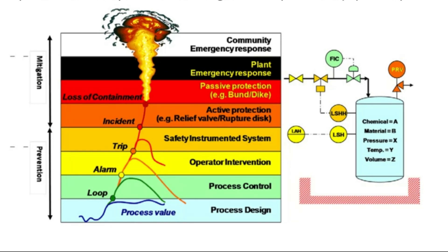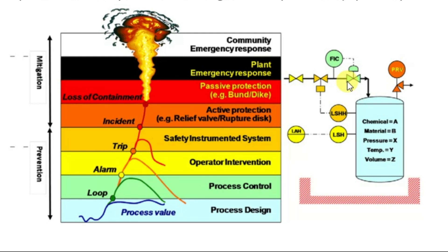A plant has to operate in the safe zone — the green zone. And then further, when limits are exceeded, we can understand this using a small P&ID. There is a chemical tank which has a hydrogen chloride facility, for example. The required chemical is being sent into the tank using an isolation valve, emergency block valve, and flow control valve. Inside the tank, pressure, temperature, and volume (level) are being measured. Based on the level, if the level is going down, the control valve operates using a flow indicating controller and admits additional chemical into the tank.